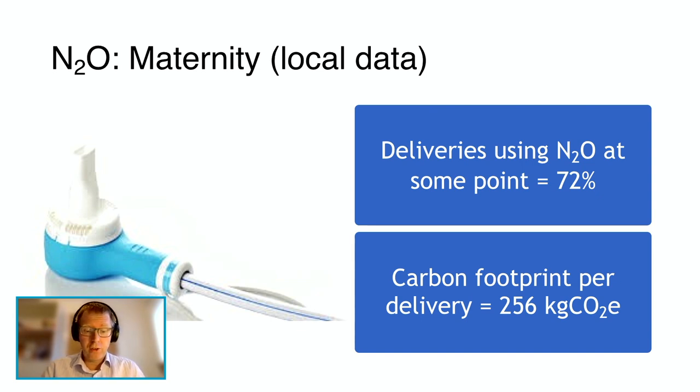When faced with our massive nitrous oxide carbon footprint, we started the nitrous oxide mitigation project, going back to basics. We studied clinician behaviours and beliefs and tried to establish if there actually was a role for nitrous oxide in modern anaesthetic practice. We studied hospital schematics to understand which clinical areas were supplied with nitrous oxide, and after engaging with clinicians, turned off and decommissioned almost all manifolds — saving not only on waste but also on capital outlay for maintenance. We aim to decommission all nitrous oxide manifolds and offer portable cylinders on anaesthetic machines where clinicians still feel it is a requirement, such as in obstetrics and paediatric theatres.